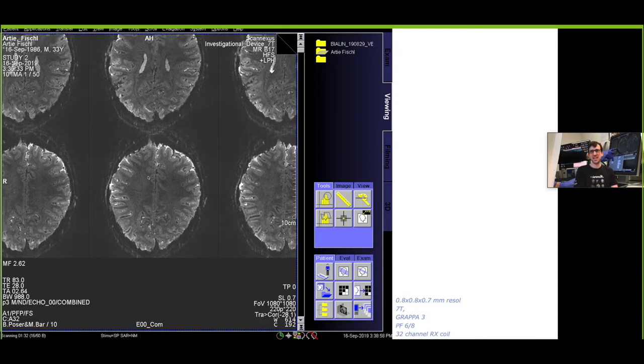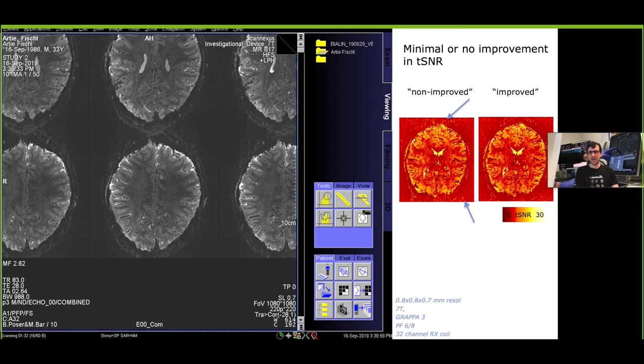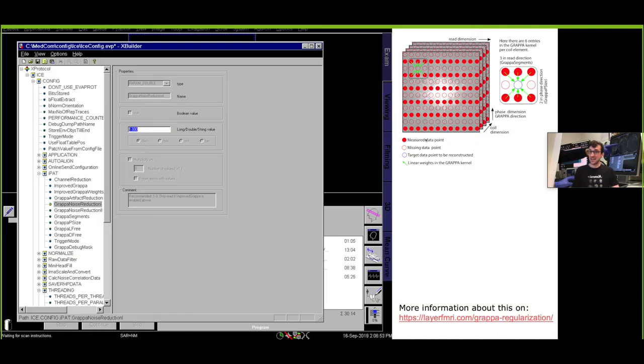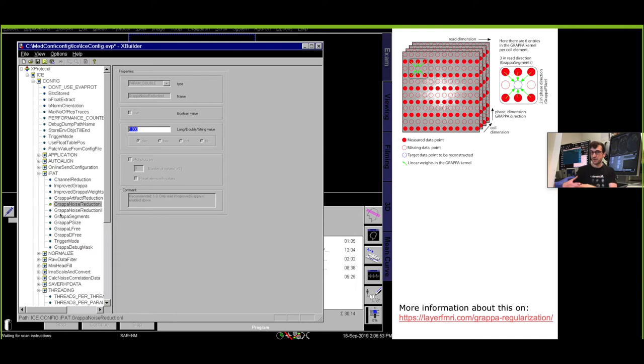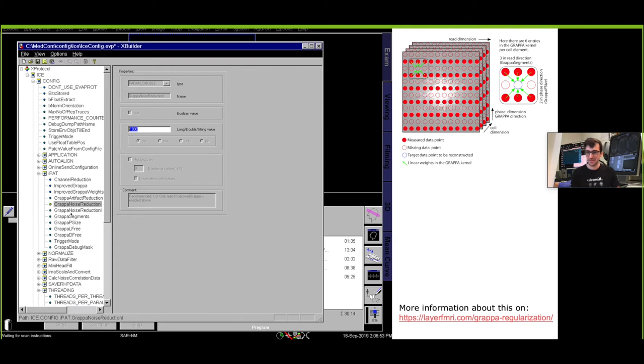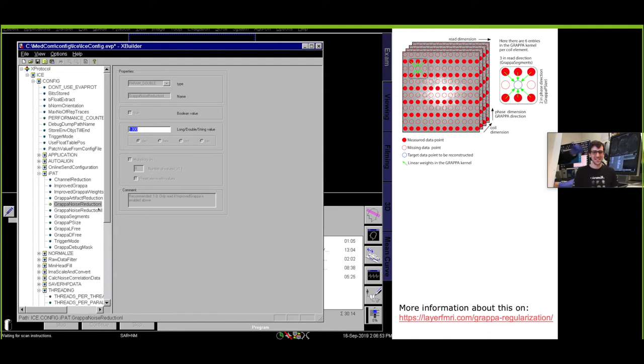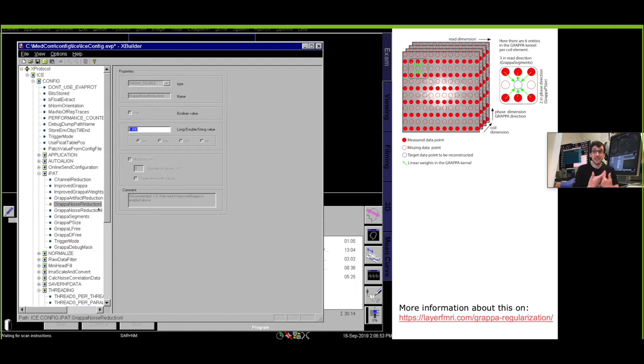Switching on Improved GRAPPA does not have a huge effect on its own. Here you can see with and without Improved GRAPPA, the shading is a bit different, the tSNR however is rather comparable. The reason why I still switch it on is that because as soon as I switch it on there are all these other parameters which suddenly now become used before they were just ignored. One of the most effective parameters is this parameter here called PAT Noise, the GRAPPA Noise Reduction One parameter which is again a weird terminology for basically just a regularization strength.